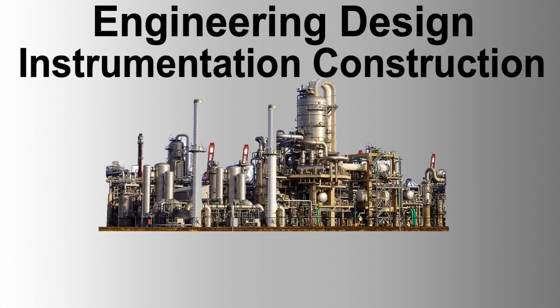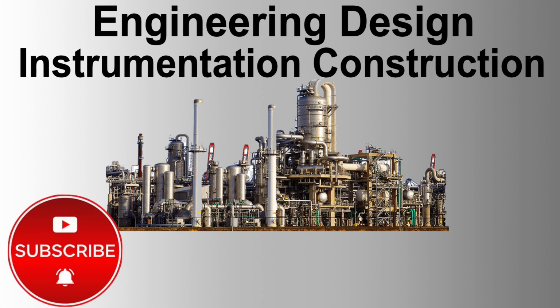Instrument impulse lines. All impulse piping shall be self-draining and in general be run with an incline to ensure adequate fall back to the process connection. The slope of the impulse pipework shall be down from the tapping point for liquids and up from the tapping point for gas service unless special provisions are made for venting and draining. Impulse lines shall be kept as short as possible, consistent with good practice and accessibility. Vents and drain lines shall be connected as per the piping installation design.